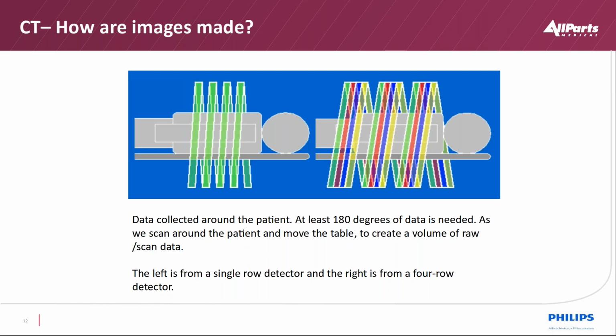On the slide on the far right, the multicolored one, that's a 4-row detector. Then we get into 16, 64. So if you think about it, we're rotating around the patient. Now, if we move the table at the same time, we're creating a volumetric data set. And out of that data set, we can project images and process them. So that's what multi-row gives us, the ability to collect data quicker. Now, the downside is we need each one of those rows to have the same amount of energy so that we can reproduce the image in the same consistent way for each of those rows.